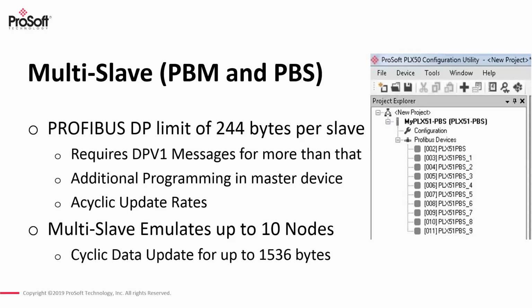So that's a really nice feature that, for some slave applications, can give you much better performance than some of the other ways of doing it with DPV1 messages. It really eases the amount of setup and configuration that needs to be done. And then lastly, it gives you update rates that are deterministic, based on cyclic I/O data of the Profibus DP network.